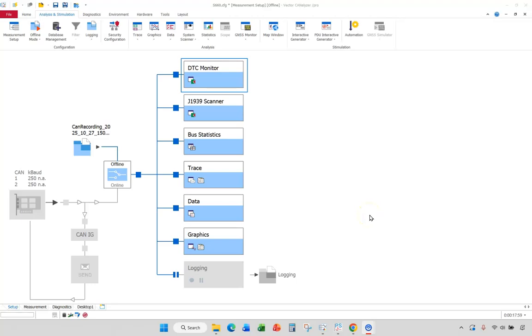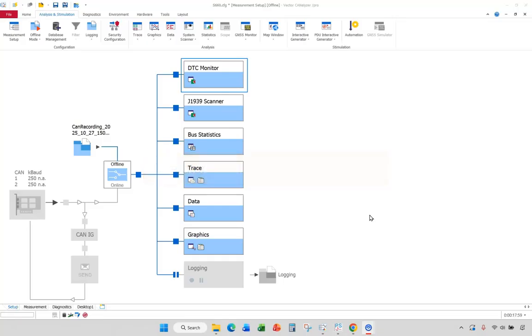This is the 23rd episode of Advanced J1939 for Technicians. In this episode, I'll look at a real problem that occurred with a John Deere S660 combine that I was working with recently. The operator complaints were that the display would sometimes go blank, the data would go blank from the display, that there would be diagnostic trouble codes.